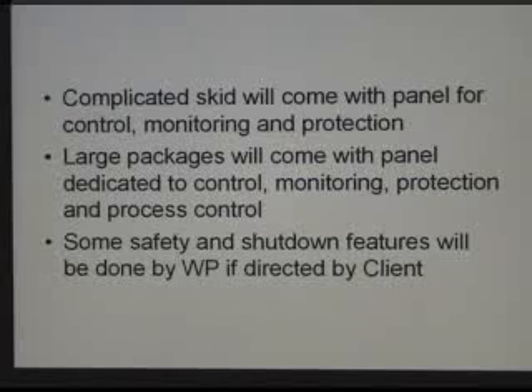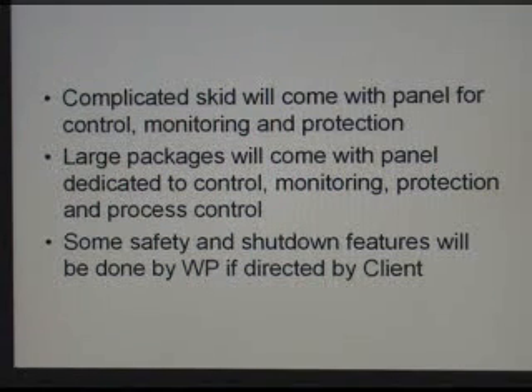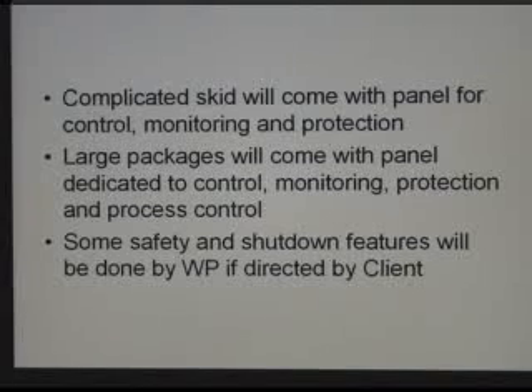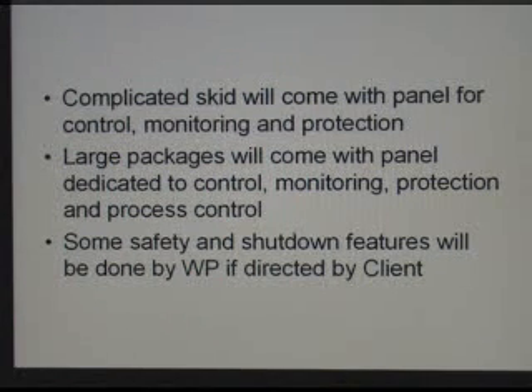Some safety and shutdown features will be done by Worley-Parsons if directed by the client. In some cases, the client says we want to have our own dedicated safety integrated system that all of the shutdown features get wired to instead of the vendor's control panel. And so we have an interesting situation sometimes where we have to split signals so that the vendor panel and the safety system both work in parallel with each other.